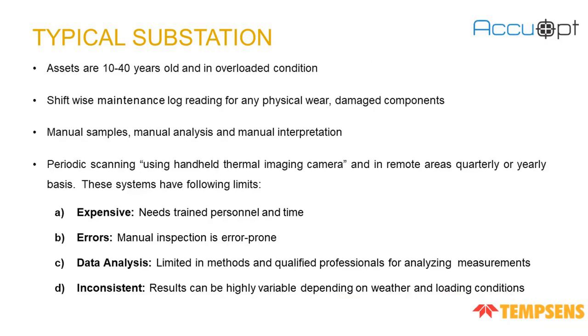The typical substation consists of assets which are 10 to 40 years old, and many of them are in overloaded condition. Maintenance involves shift-wise log reading for any physical wear, damaged components, etc. Manual samples, manual analysis, and manual interpretation. Periodic scanning is done using handheld thermal imaging cameras, and in remote areas on a quarterly or yearly basis. But these handheld thermal imaging cameras have the following limits. It is very expensive as it needs trained personnel and time. The manual inspection can be error prone, and data analysis is also very difficult as it requires qualified professionals for analyzing measurements. Results can be highly variable depending on weather and loading conditions.